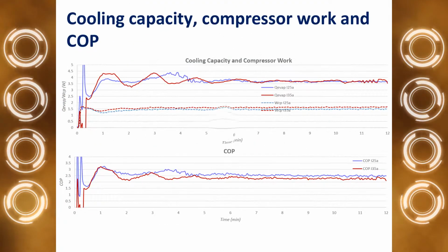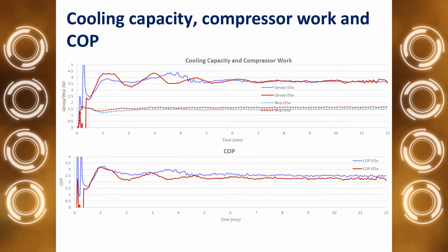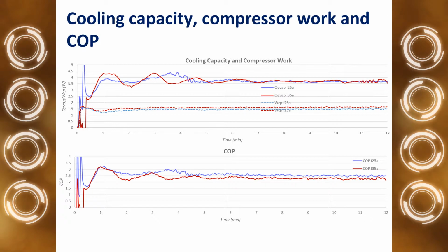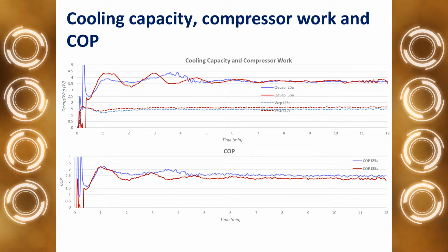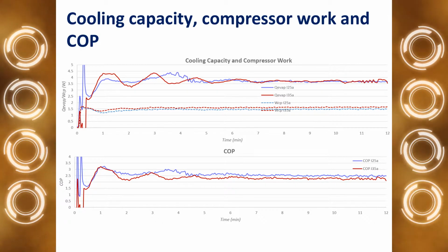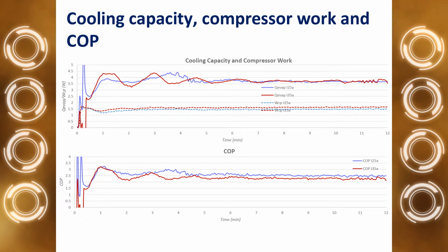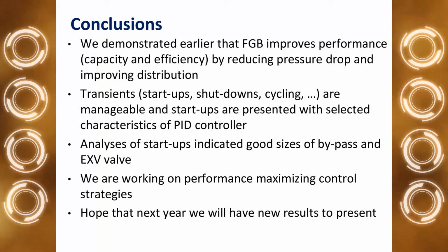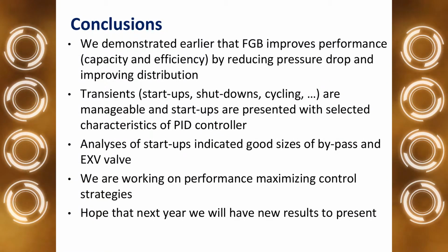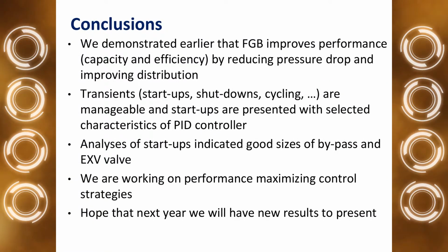And here is the comparison between capacities and compressor work in those two regimes, and we could manage it very well so far. We had more or less similar capacities and compressor work in those two conditions, and we could also control COP.